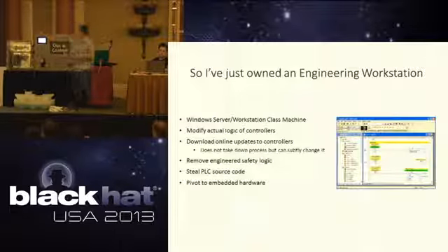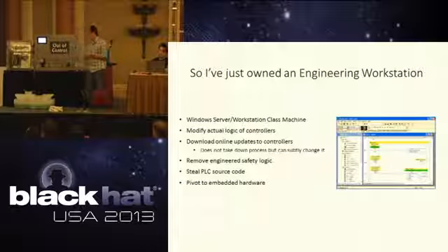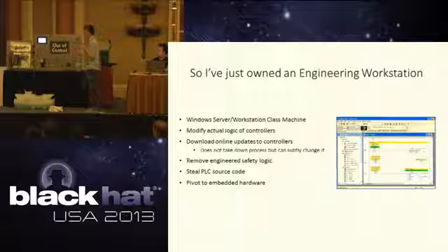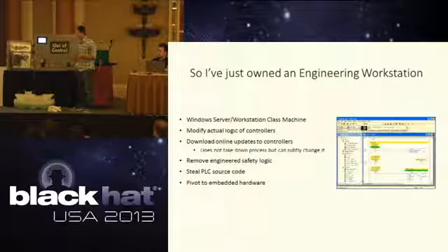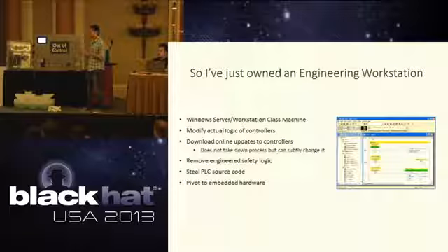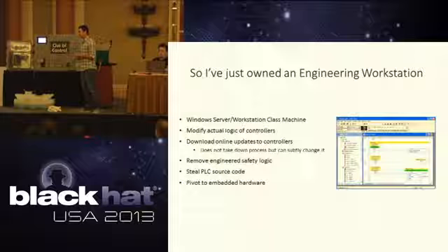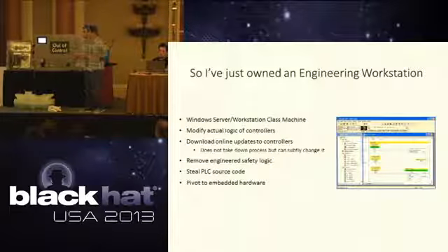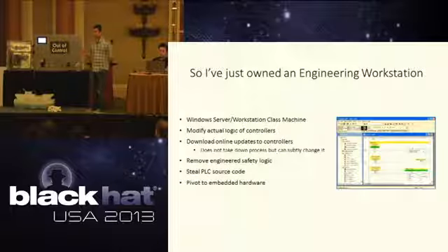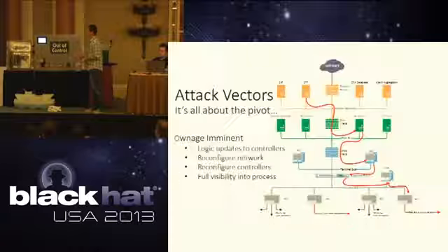So that picture up there is of an engineering workstation program, and we'll talk about this a little bit later, but the language that you write on these PLCs is not C or anything like that. It has a couple of different forms, but primarily what you'll see is what is called ladder logic. And you can see obviously why it's called that, but it's essentially an old programming language that's relay logic. So it's meant for electrical engineers, not so much programmers.